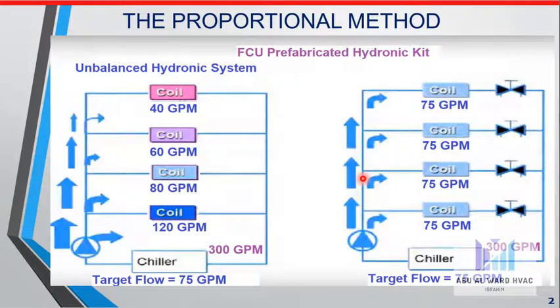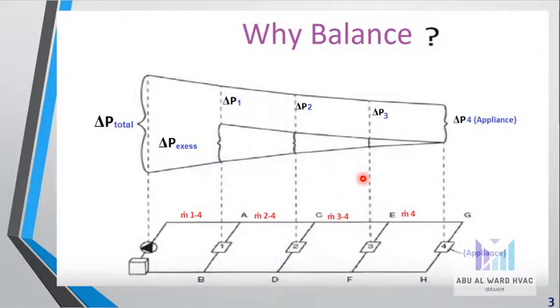Why are we using balancing? We are doing the balancing actually because near the circulator or the pump, the nearest units in the circuit or in the system will suffer from high delta P. It will have more delta P, thus the flow will be increased.